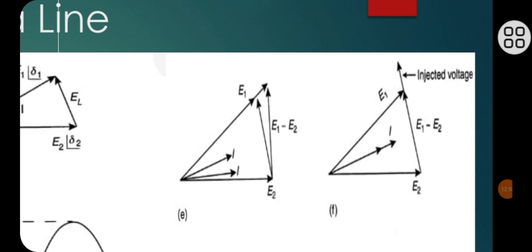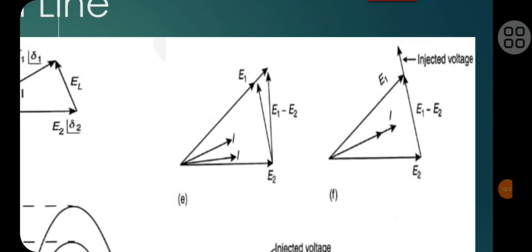When you inject a voltage in series with the line, the length of the vector E1 minus E2 is as if increasing, so your current is increasing in length, not the angle. So that means there is active power control here, not reactive power control.